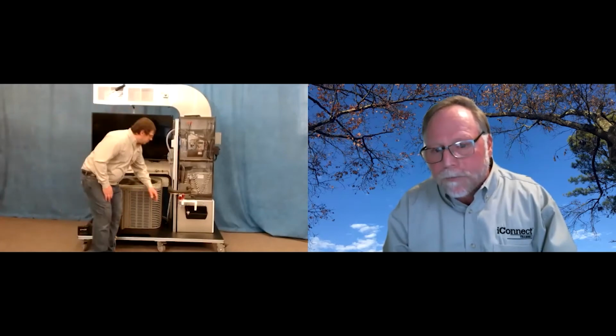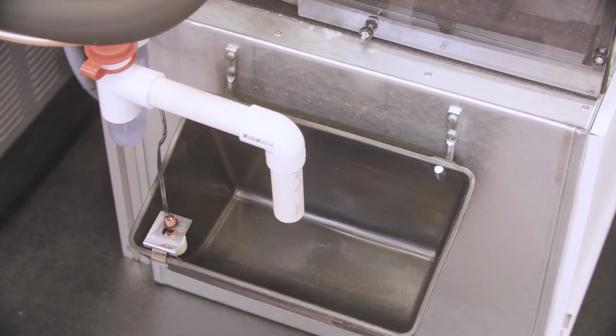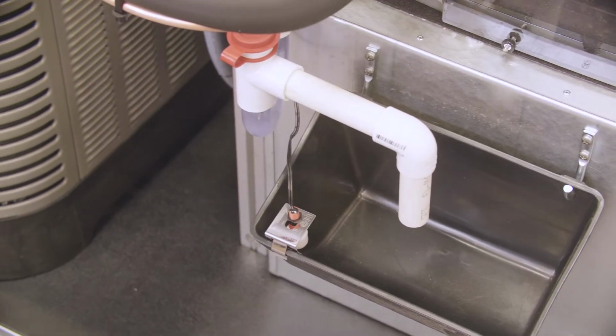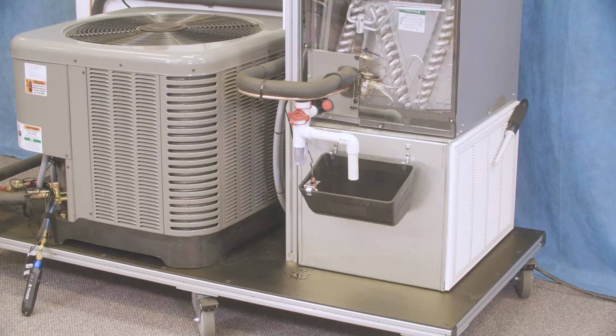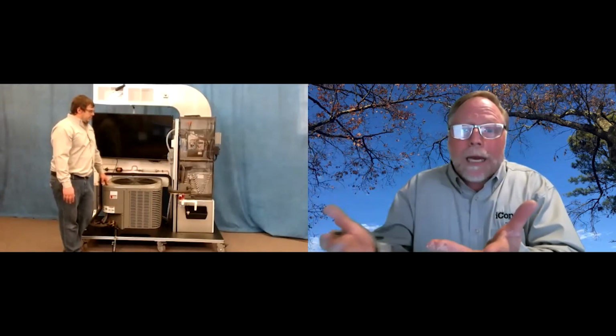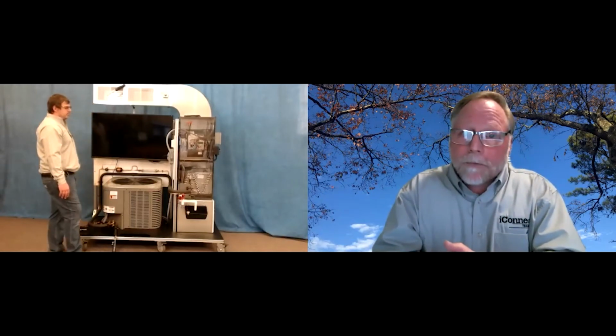Lesson 3 we're going to look at is explaining the difference on the traps. So you look down there at that condensate trap, and Nick, you'll point to the depth of that trap there. Okay, see how it comes down and comes back up? There is a particular reason for the dimensions of those traps. This trap, you can point out, is on the intake side of the motor, the blower motor. So you look at the blower motor, it's up top of the evaporator coil. So it's pulling air through the evaporator coil. Well, it's also pulling air through that condensate trap.